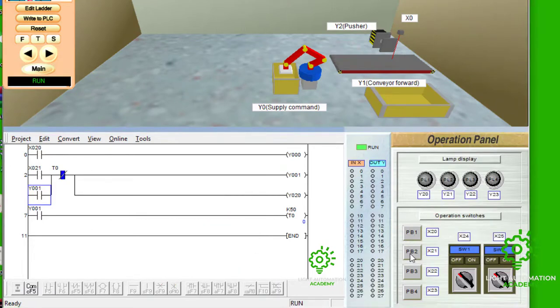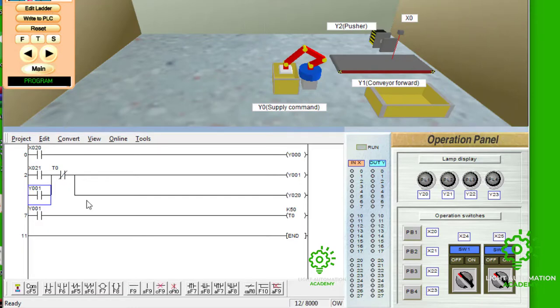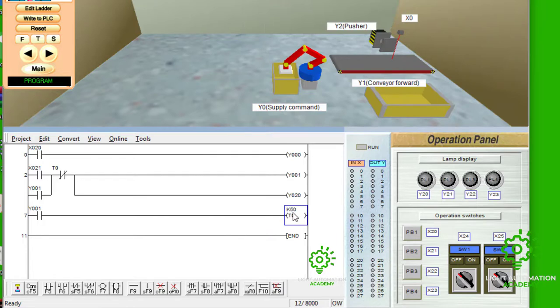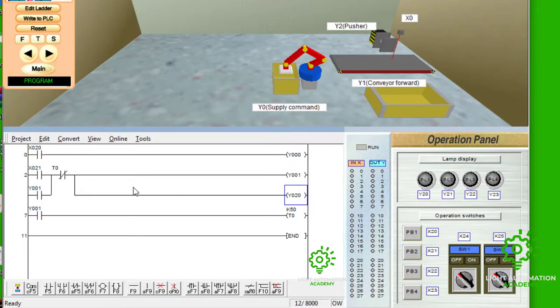When you press it once, the power continually goes to that conveyor. Then, the same thing we said to switch in this off, we introduced to you for the first time a timer. The same way a normal timer works. But this time around, we are using our conveyor to power the timer so that whenever the conveyor is on, the timer starts counting. And when it reaches 50 seconds, we use it as a normally close button to stop the conveyor. And that is exactly what we do. Also, to make the operator in the field know what is going on when the conveyor is running and when it's not running, we attach here an indicator lamp to give us information from afar when the conveyor is running and when it is not running.